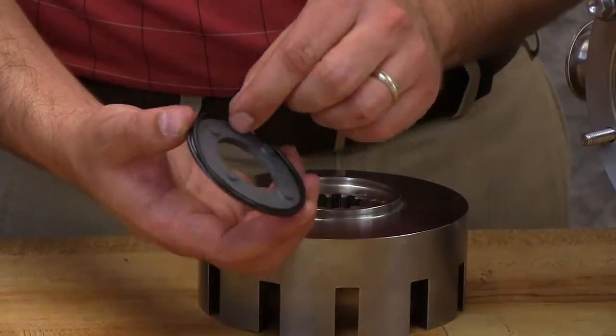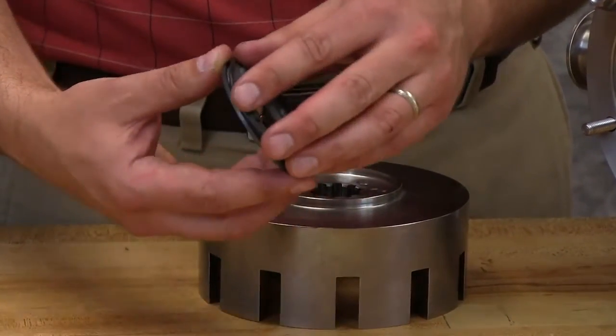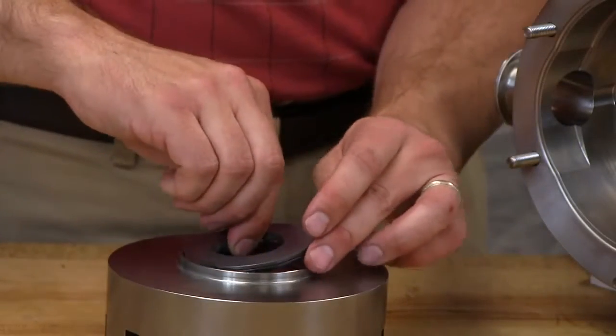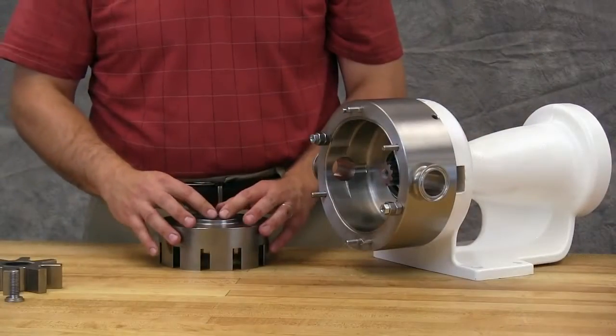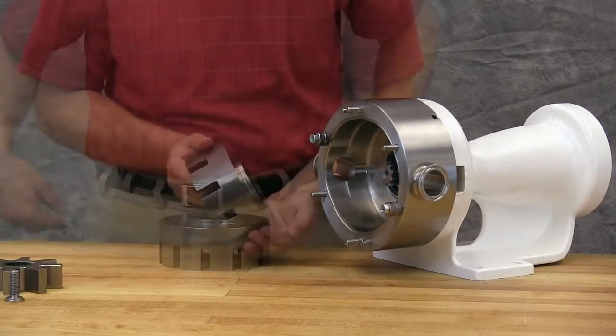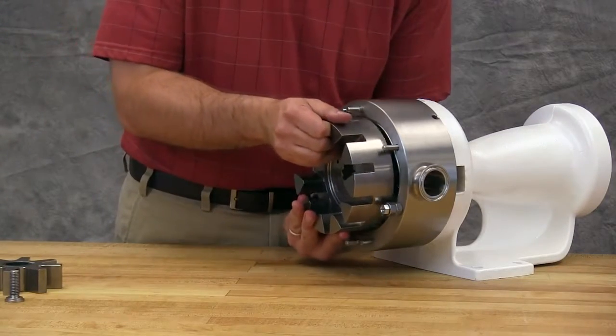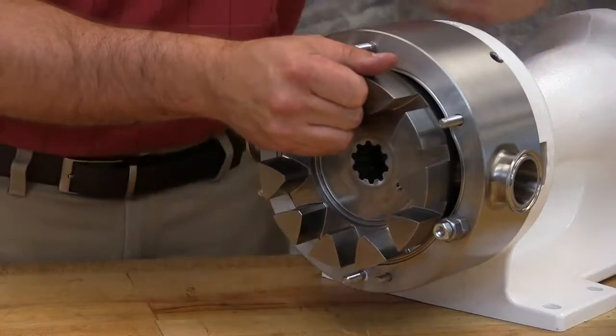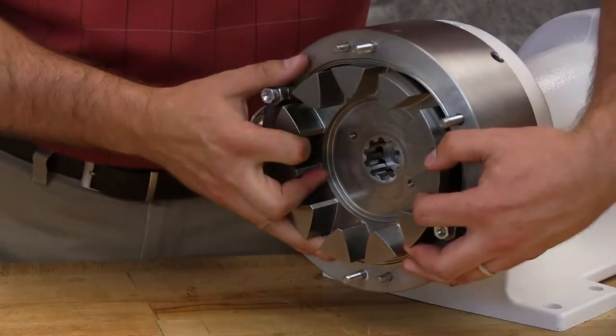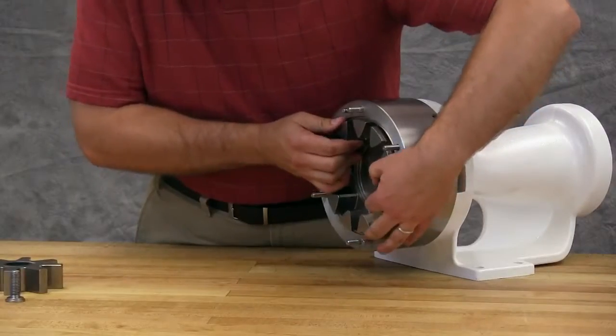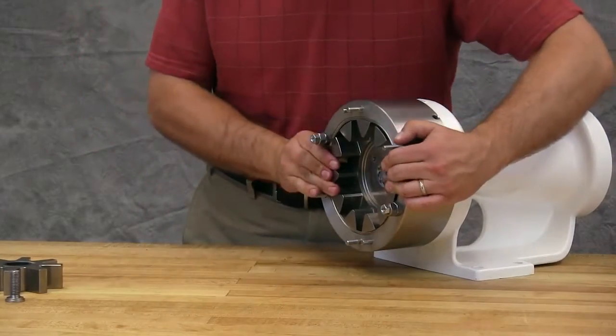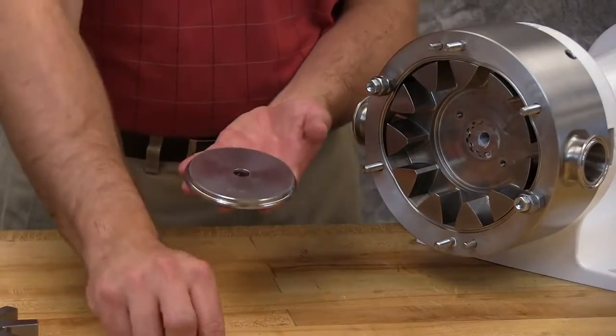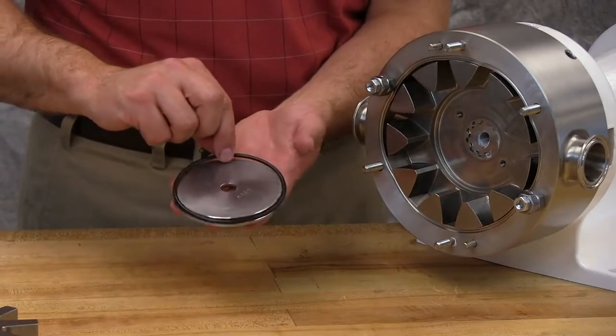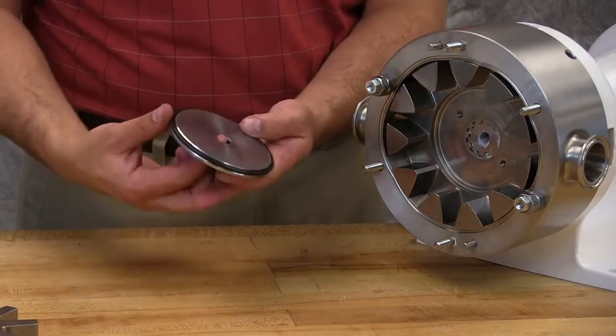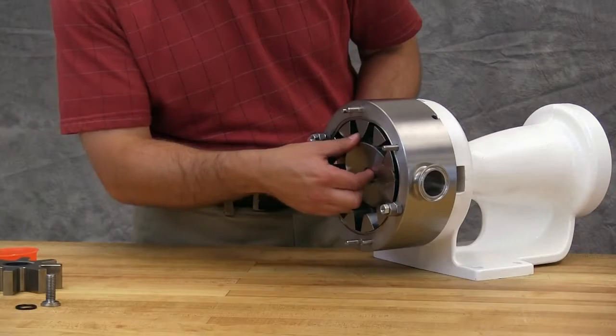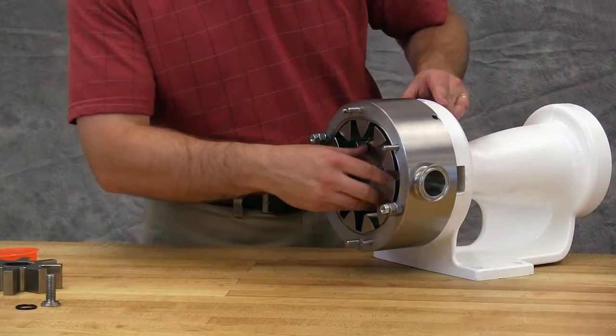Install the O-ring onto the back of the rotary face. Install the rotary face onto the backside of the rotor. Install the rotor onto the shaft by lining up the splines on both components. Take care not to damage the seal faces while installing the rotor, and ensure that the seal faces do not slip out of position. Install the rotor retainer cap O-ring onto the rotor retainer cap. Install the rotor retainer cap onto the face of the rotor.